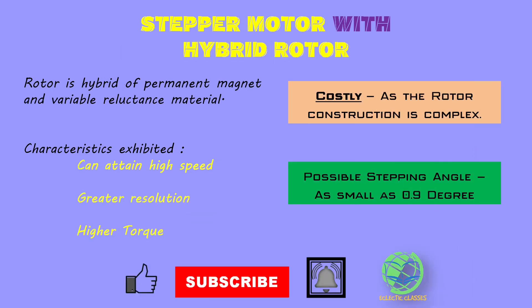Hybrid rotor: here the rotor is a hybrid between permanent magnet and variable reluctance versions. Being a hybrid of both, it has advantages of both types, which are higher resolution, speed, and torque. However, due to the hybrid rotor construction being complex, it is costly in comparison to the other two types. This is used in applications where small stepping angles are required, as we can get a stepping angle of 0.9 degrees with this type of stepper motor.